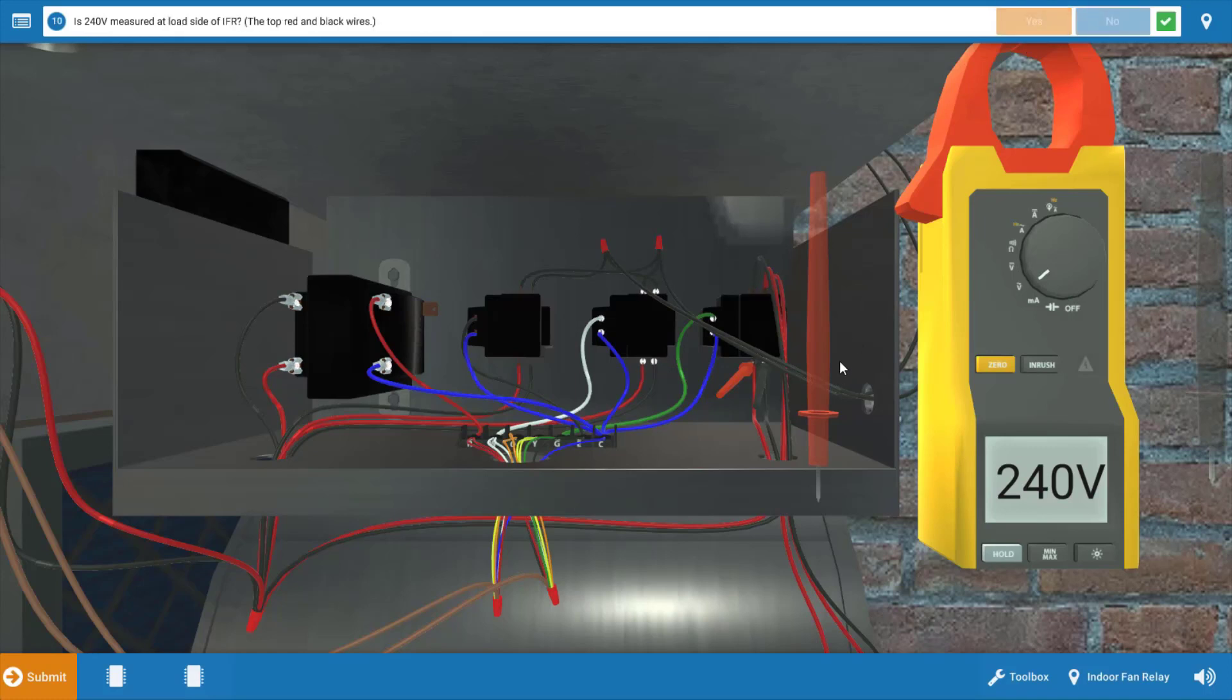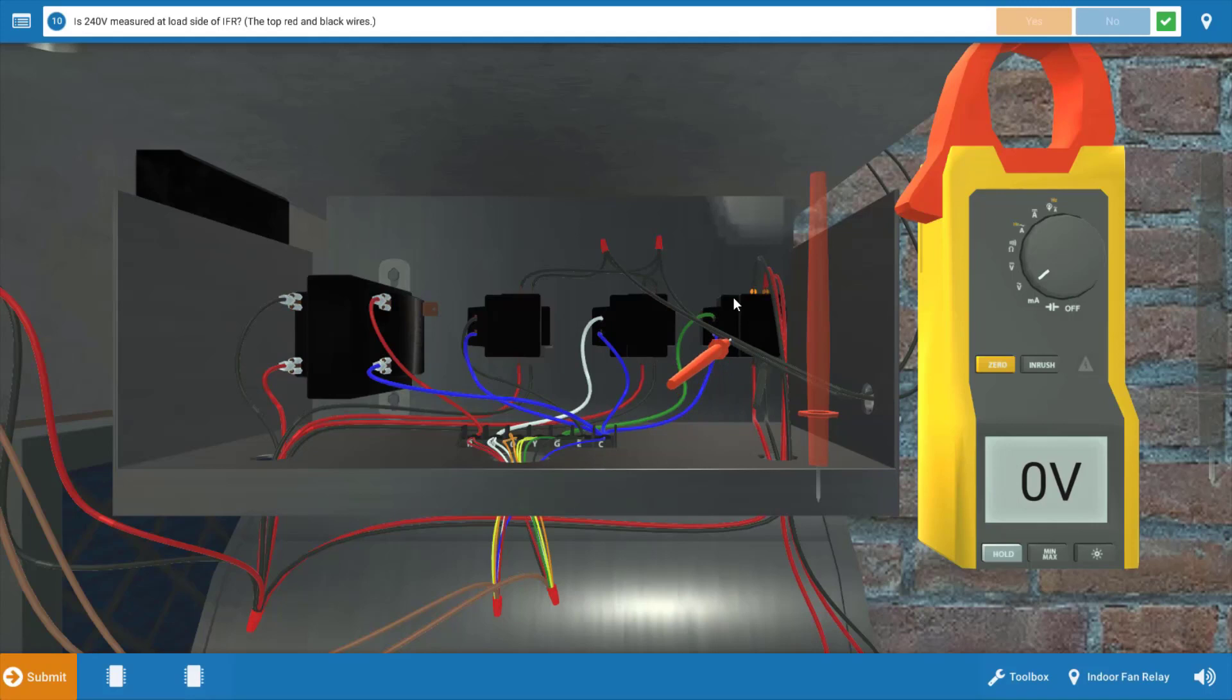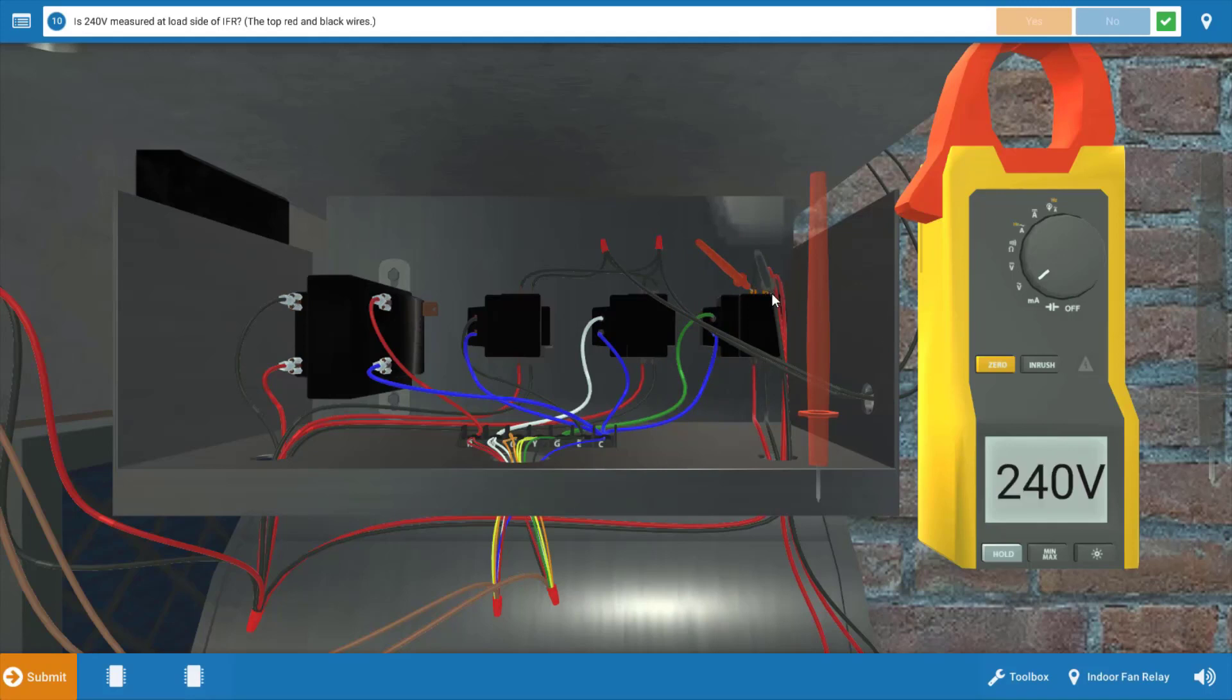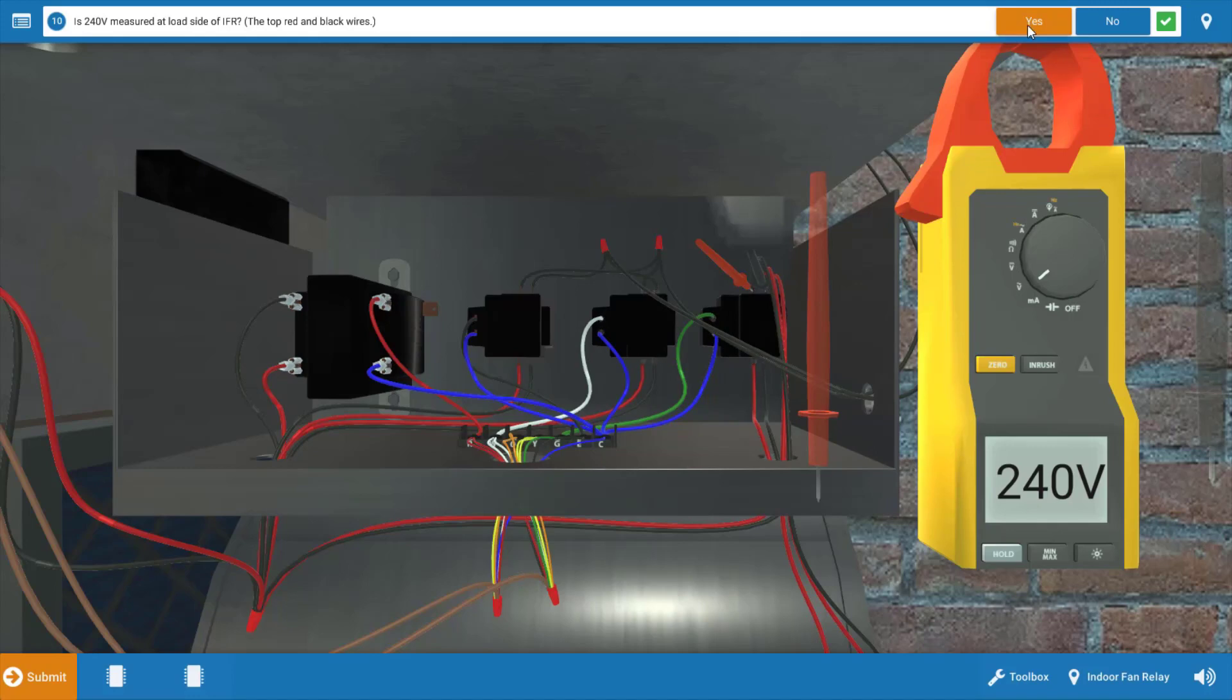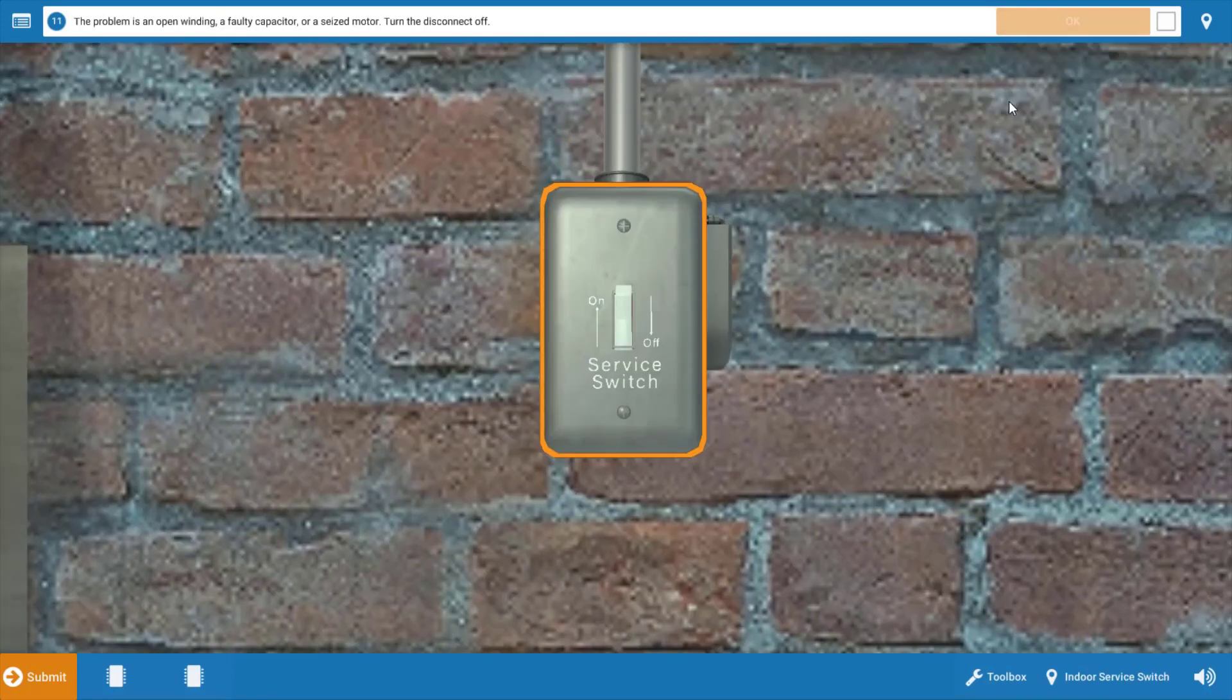Our next step is to measure at the load side of the fan relay at the top. This will verify that the contacts are actually closing and sending power to the indoor fan motor and the capacitor. We're going to take our meter leads and place them at those two glowing orange hotspots. Again, we have 240 volts. This eliminates the indoor fan relay as a possible cause here. It also eliminates the thermostat, the fan switch within the thermostat, because we have power to the relay coil. Click yes on the procedure guide.